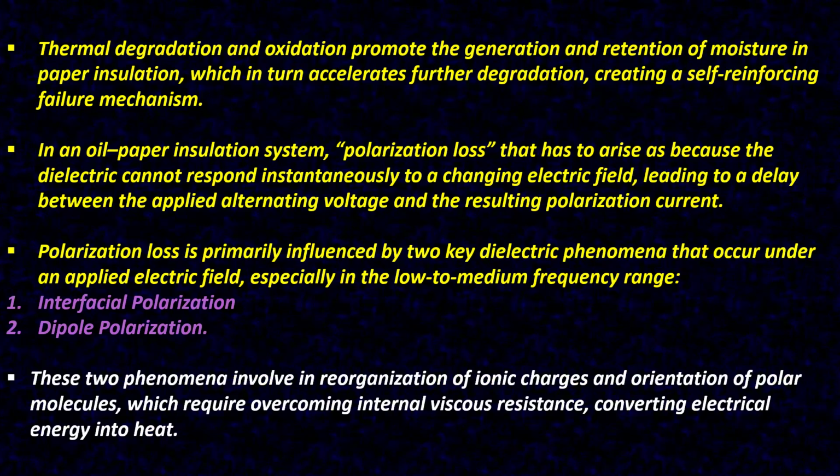Thermal degradation and oxidation promote the generation and retention of moisture in paper insulation, which in turn accelerates further degradation, creating a self-reinforcing failure mechanism.